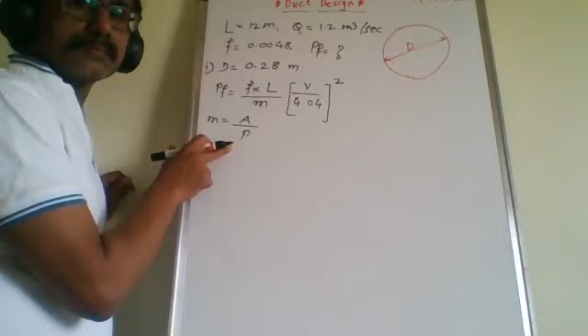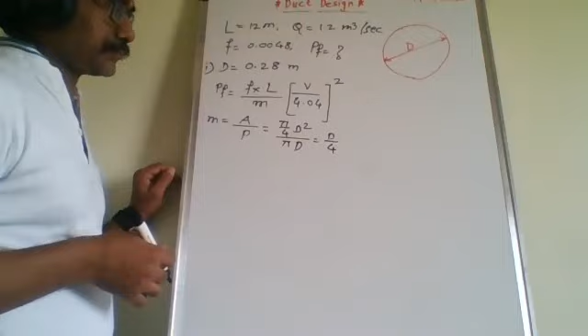Okay. So as it is a circular duct, we have the area pi by 4 d square and the perimeter, that is nothing but pi d. So we will have M equal to d by 4 for the circular duct. Then V is nothing but the mean velocity of the air passing through the duct in meter per second. So we can first find out this M. The diameter is 0.28 meter divided by 4. So hydraulic mean radius comes equal to 0.07 meter.